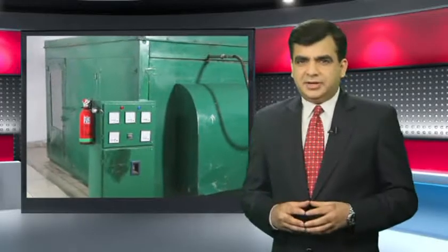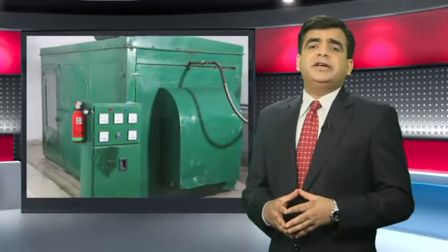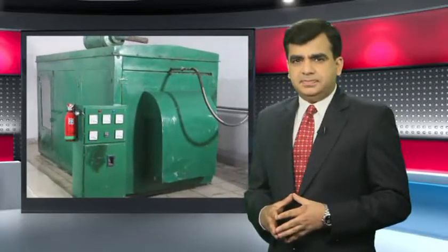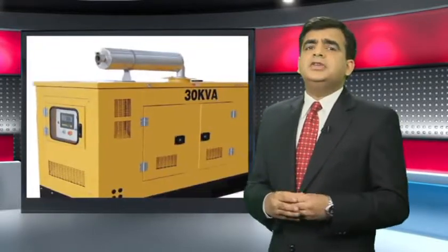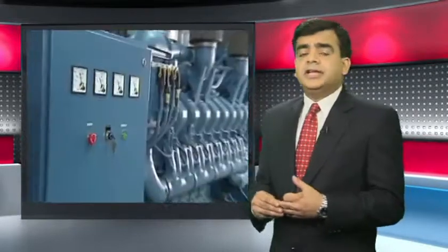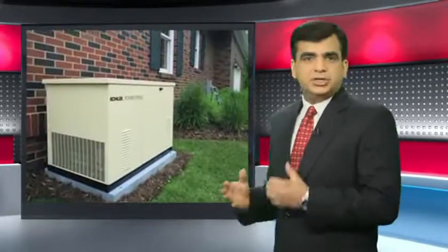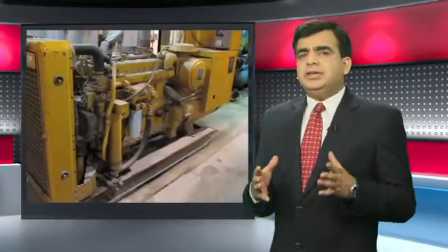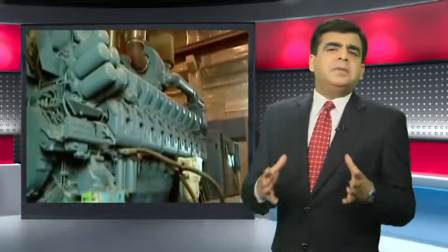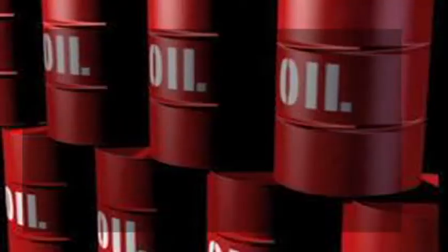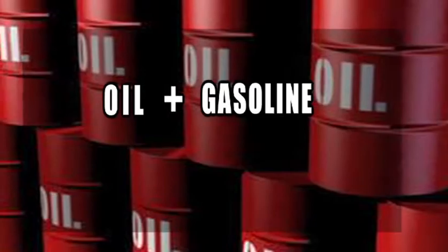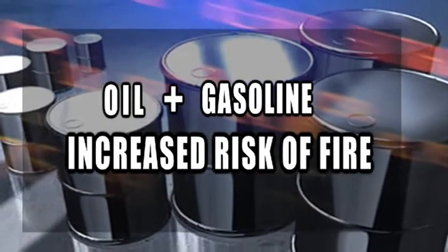Another water mist application we have designed is the Ceasefire Generator Auto-Quell System. But first, let's understand the fire risks faced by generators. Generators are usually gasoline or oil-powered. They are primarily used at manufacturing, commercial, industrial facilities, and residential premises. The amount of heat generated by them is phenomenal, and when you add the presence of oil and gasoline to the equation, the risk of fire increases.